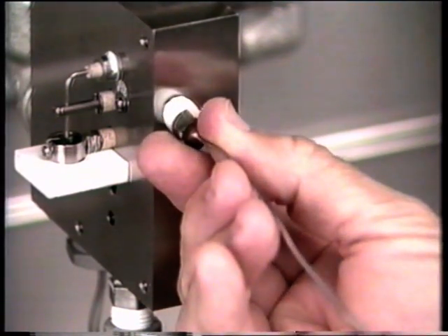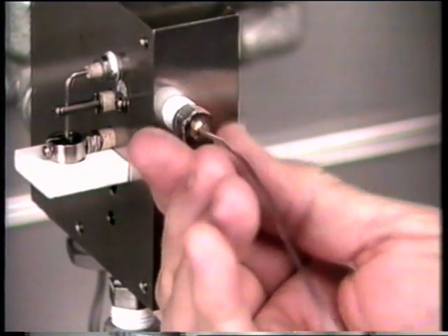Install the carrier and hydrogen inlets and the air inlet. Install the coax shields of the bias ignite and signal cables. Connect the bias ignite center conductor to the collector electrode. Once all detector components have been properly aligned, tighten any loose nuts or washers.